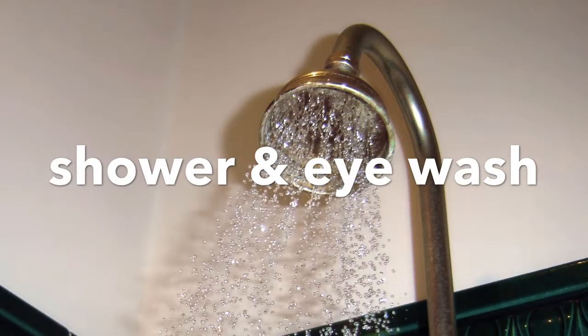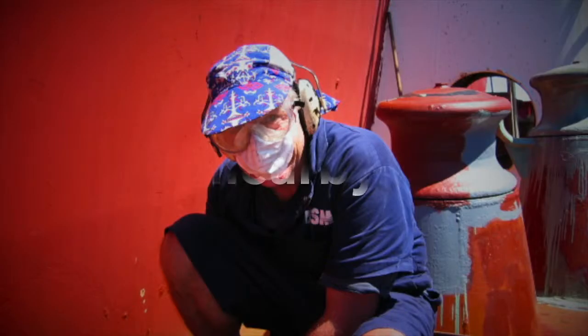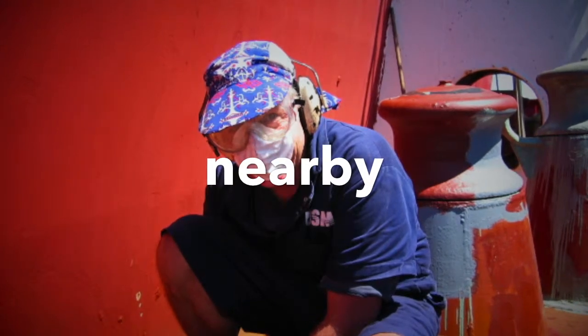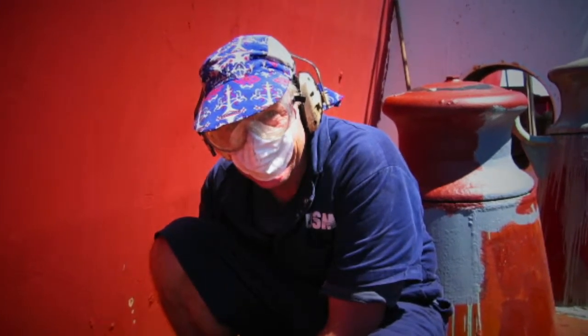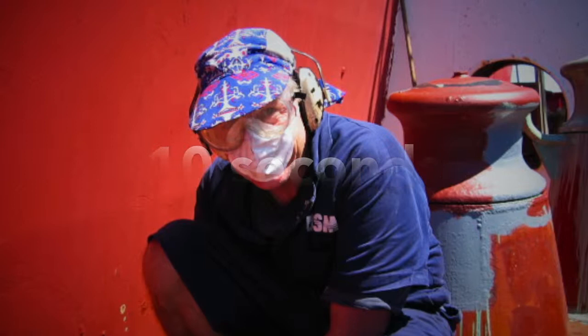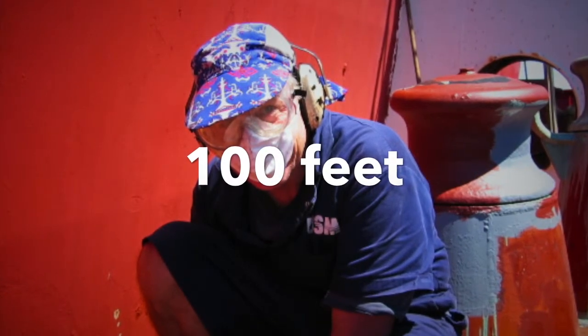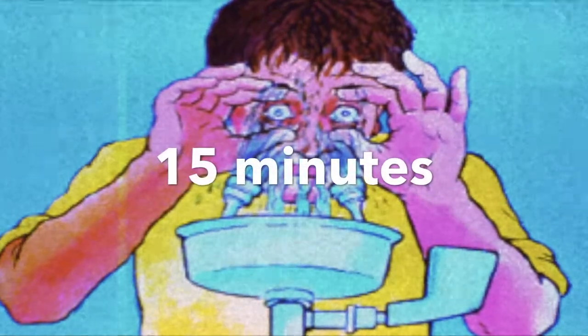Our next emergency equipment is the shower or eye washes. These need to be located where chemicals are stored or where we are using chemicals. It should be within 10 seconds or no more than 100 feet away from the work area. You will flush the affected areas a full 15 minutes and seek medical attention.